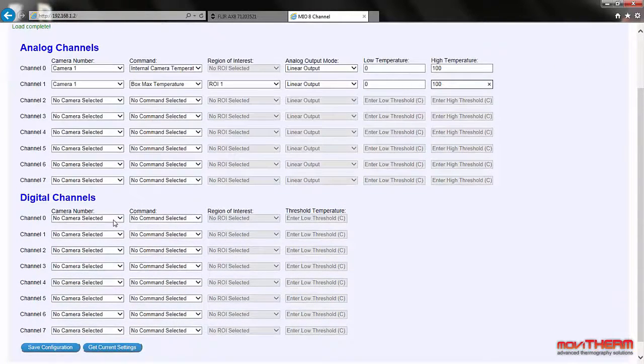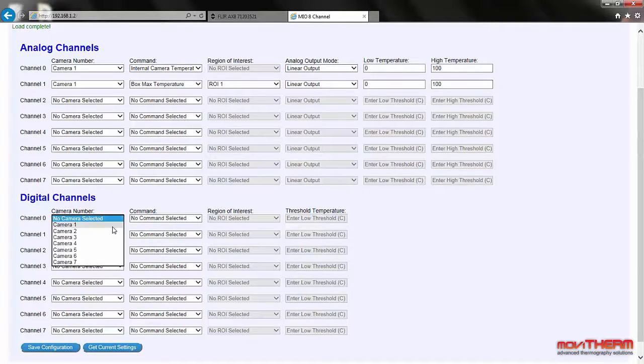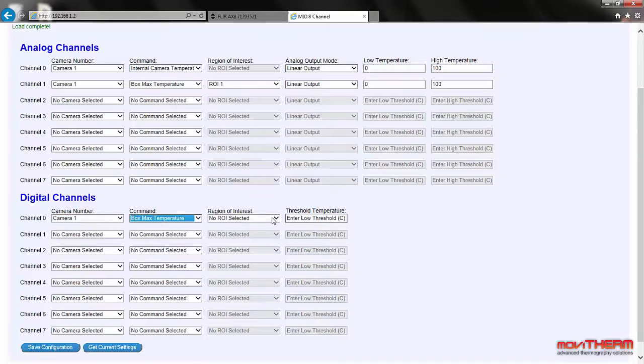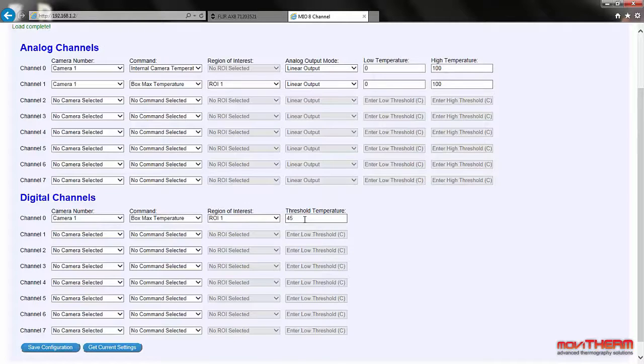We also want to set a digital output to illuminate a front panel indicator when the temperature goes above our alarm limit. We start by assigning camera 1 to digital channel 0. Under region of interest, we select ROI 1 to map the previously defined box region. We finish up by setting the threshold temperature to 45 degrees Celsius. We have now mapped the internal camera temperature to the upper analog display and the box maximum temperature to the lower analog display. The top alarm lamp is set to light up when the box maximum climbs above 45 degrees Celsius. The last step is to save the configuration to make it active — click save configuration.